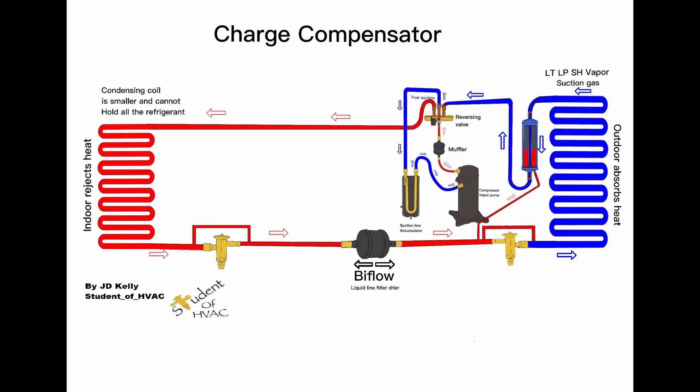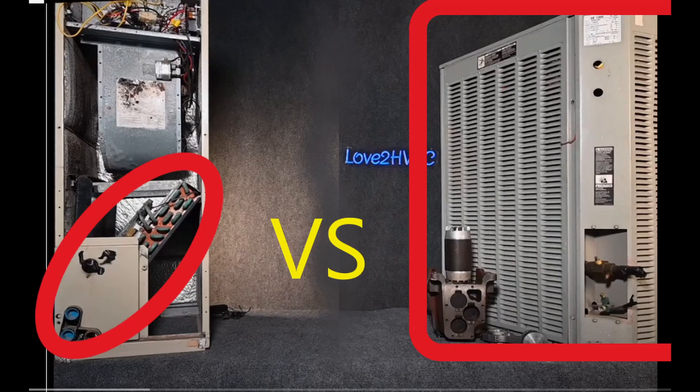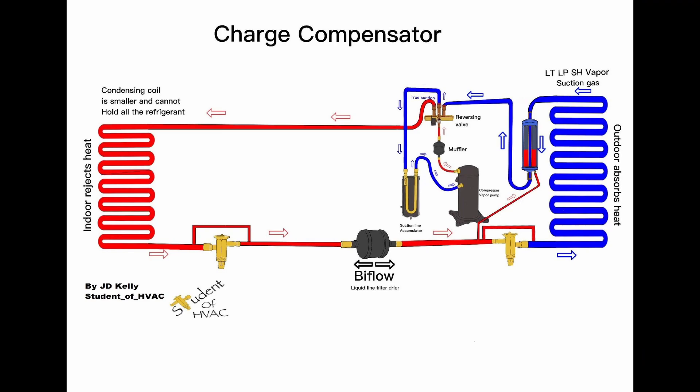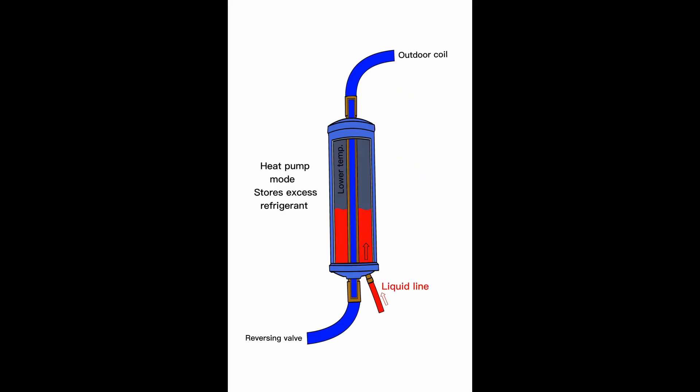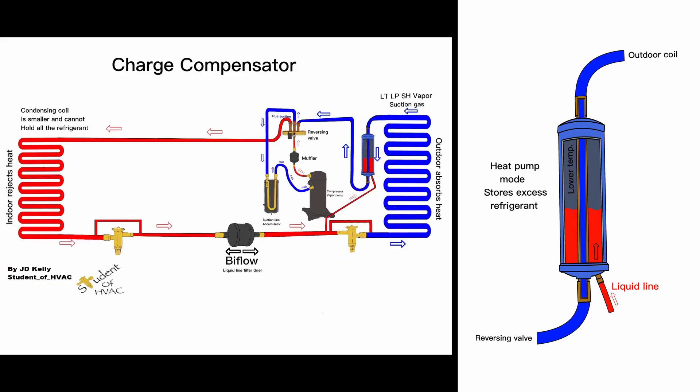When we went into heat pump mode, the indoor coil became the condensing coil and there isn't enough volume in that indoor coil. So we had extra refrigerant we had to put somewhere. In that case, that extra refrigerant went into the charge compensator because that vapor line was now a low temperature, low pressure. It allowed for that excess liquid refrigerant to migrate into the charge compensator and we had a place to store it.